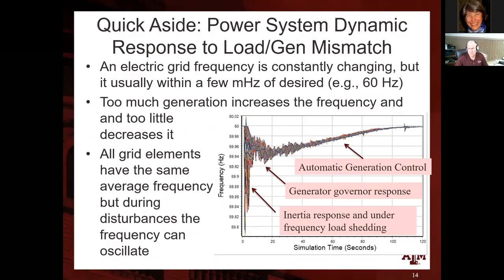So one of the things we power engineers do, and one of the things that we did a lot of on this project, was to look at the dynamic response of the grid to large events, and a large event might be the loss of a significant amount of generation. The graph there shows how the grid frequency will respond when you lose a large amount of generation. And what happens is, in steady state, everywhere in the grid has the exact same average frequency. But during disturbances, those frequencies can vary as the grid actually oscillates. And I'll show you some examples of that in just a second.